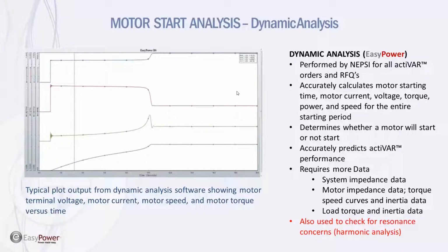Northeast Power Systems uses EasyPower to perform dynamic analysis to determine the performance of the actiVAR. I'm going to get into a case study in which we use the EasyPower to do harmonic analysis, because we are applying a capacitor bank during that starting period. So it's important that you do harmonic analysis to simulate what's going on for the on period.